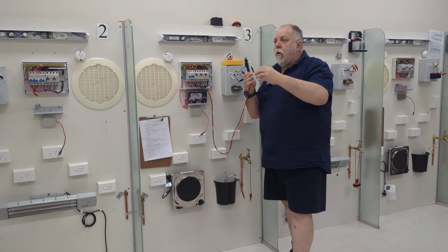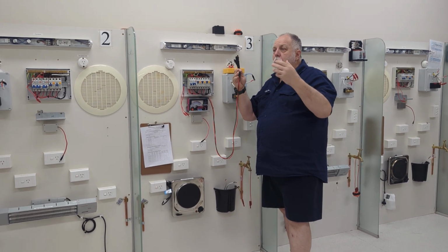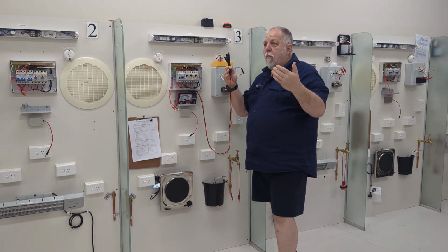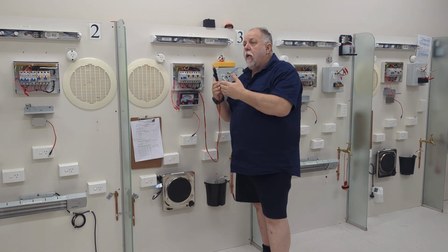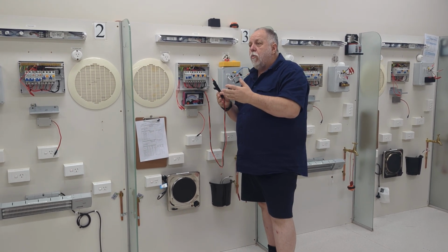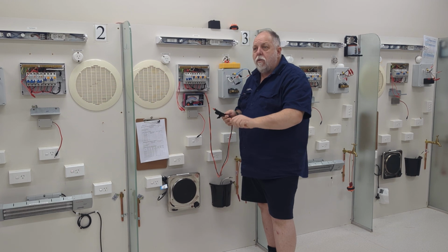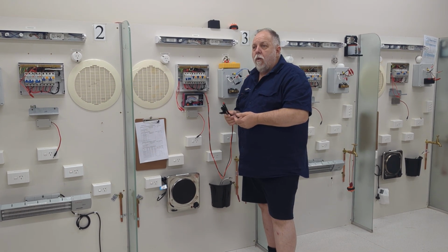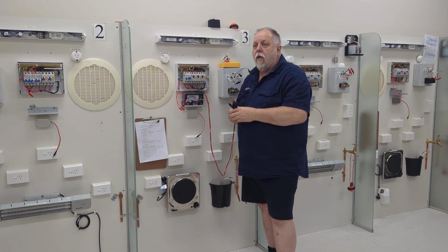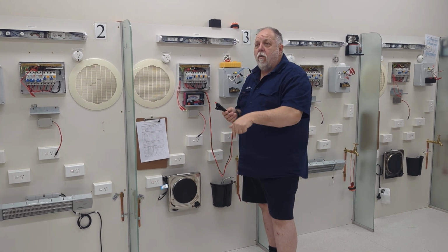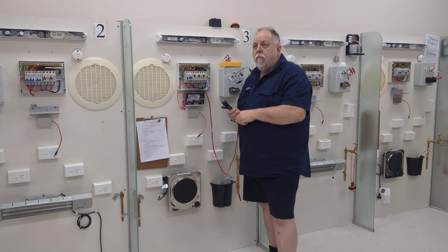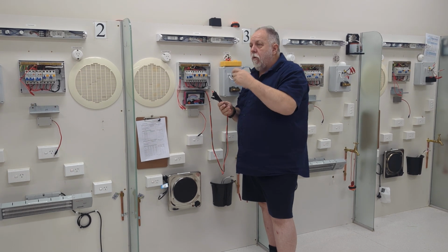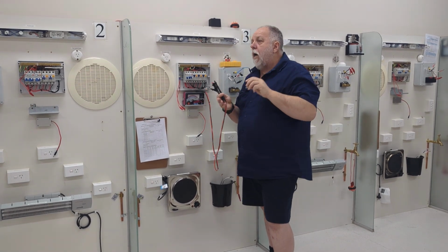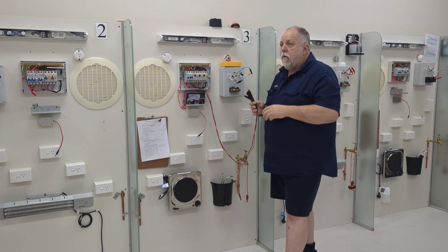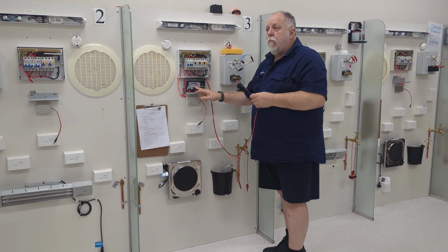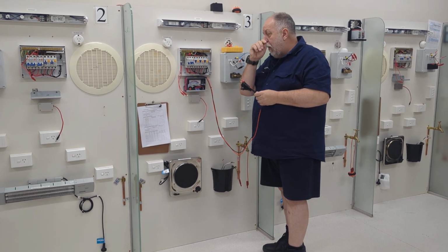AC is alternating, right? So as it gets further away, the arc gets weaker. With DC, I've seen it jump nearly a meter, all right? And it's very deadly. That's why I say to guys working on low voltage batteries and all that stuff with spanners, be very wary, all right? I've seen somebody nearly get killed on a 24 volt battery, but it had 700 amps sitting across the terminals. So you've got to be very careful. With DC, if you think you're going to pull away and get away from the arc, it will grab and hold you, all right? So we use DC here, it finds faults and weaknesses in cables much easier, all right?